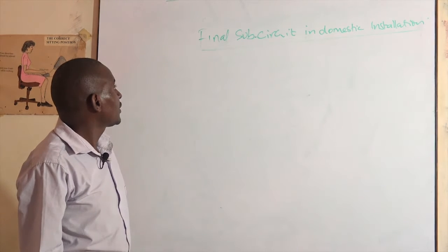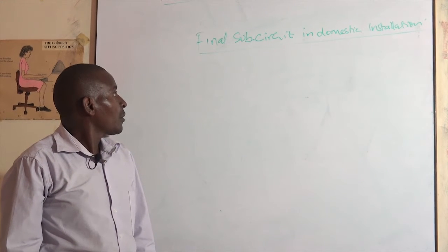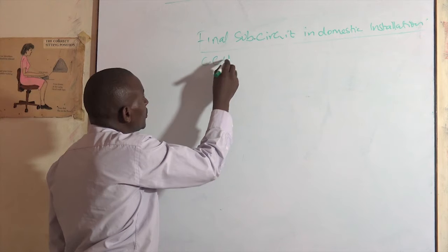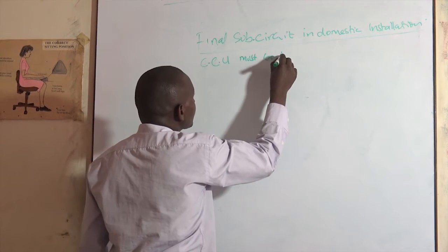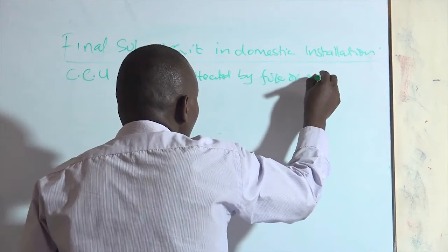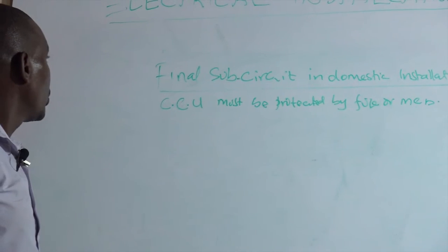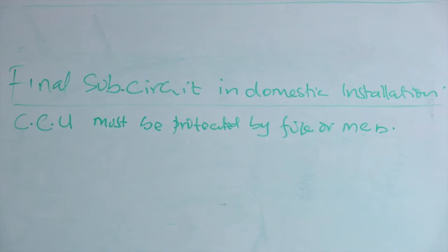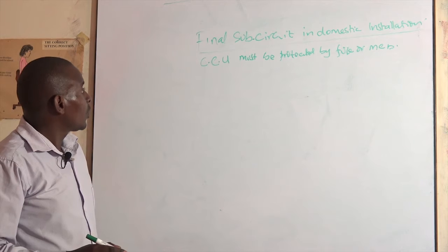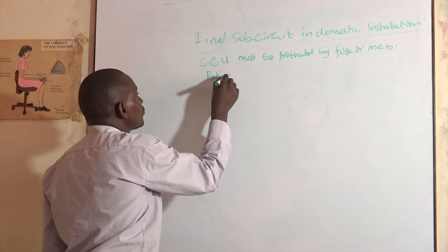From our last discussion we found out that, according to the IEE regulation, all circuits forming part of a domestic installation must start at the CCU and must be protected by a fuse or MCB. What determines the size of the fuse or the MCB is its current rating.